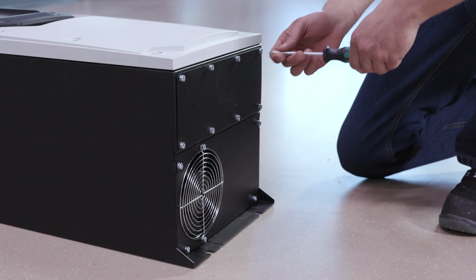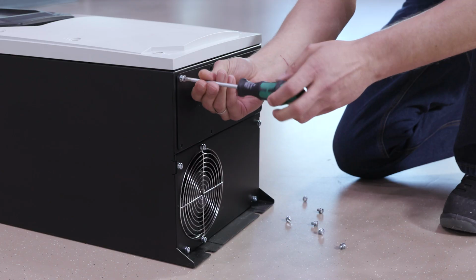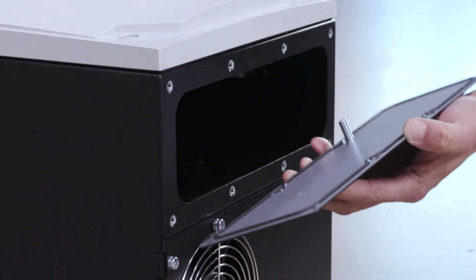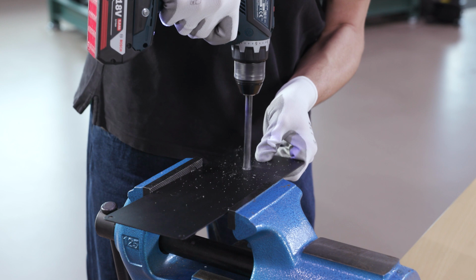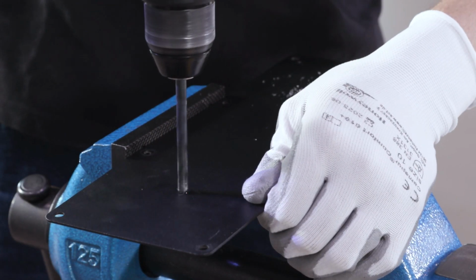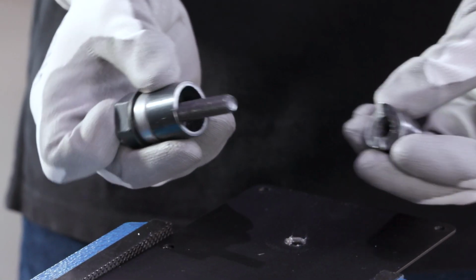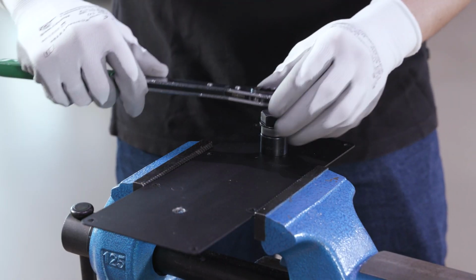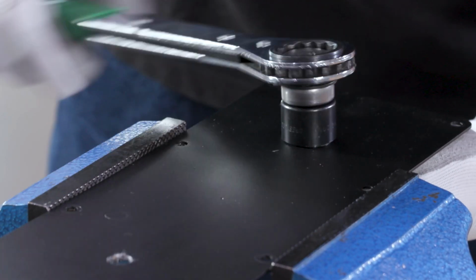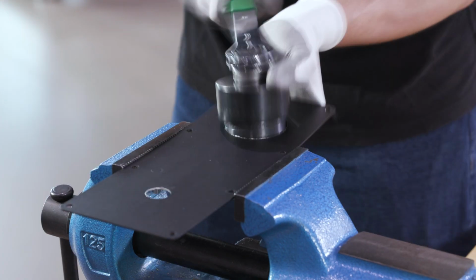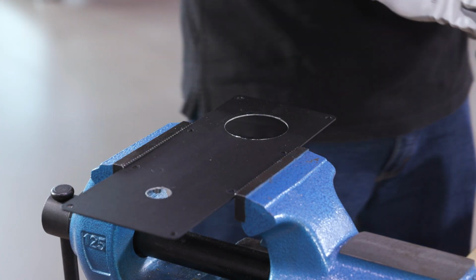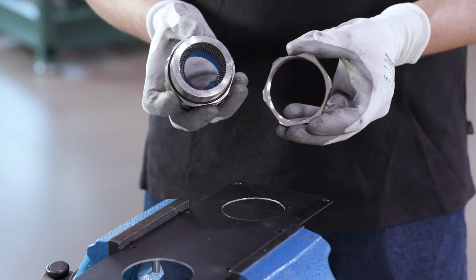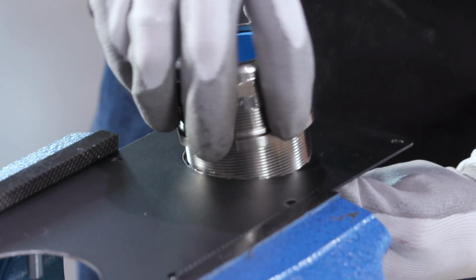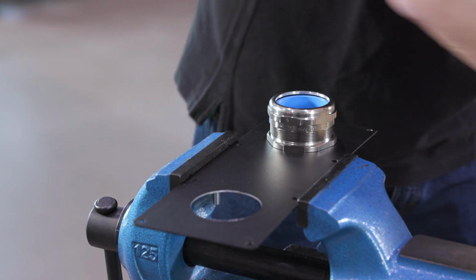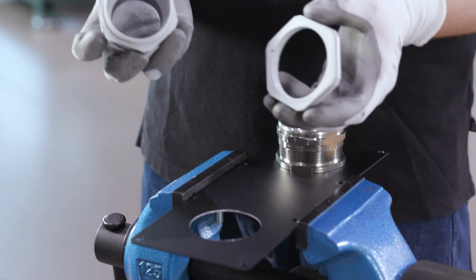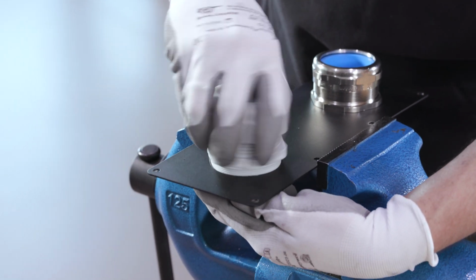Before mounting, remove the cable bushing plate for the cable glands and drill or press the corresponding holes. Then fix the EMC cable gland for the motor cable and the cable gland for the voltage supply cables and control cables.